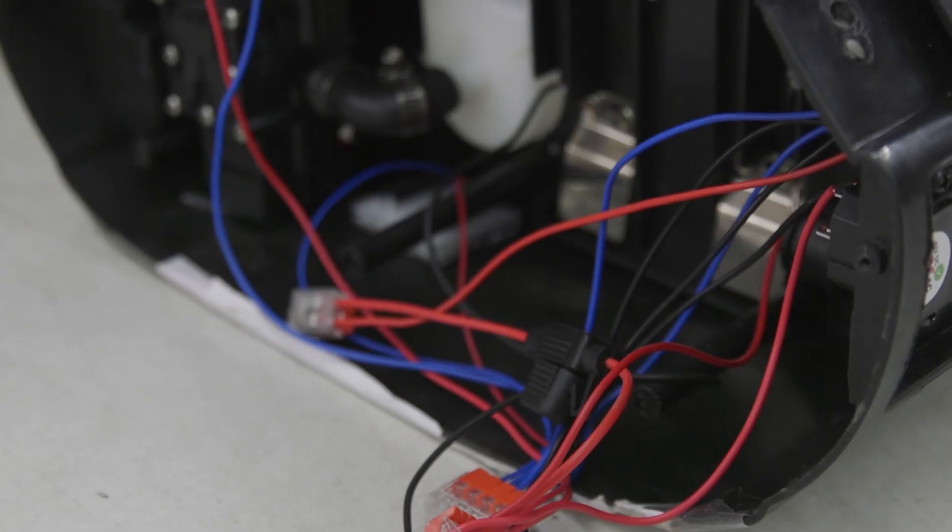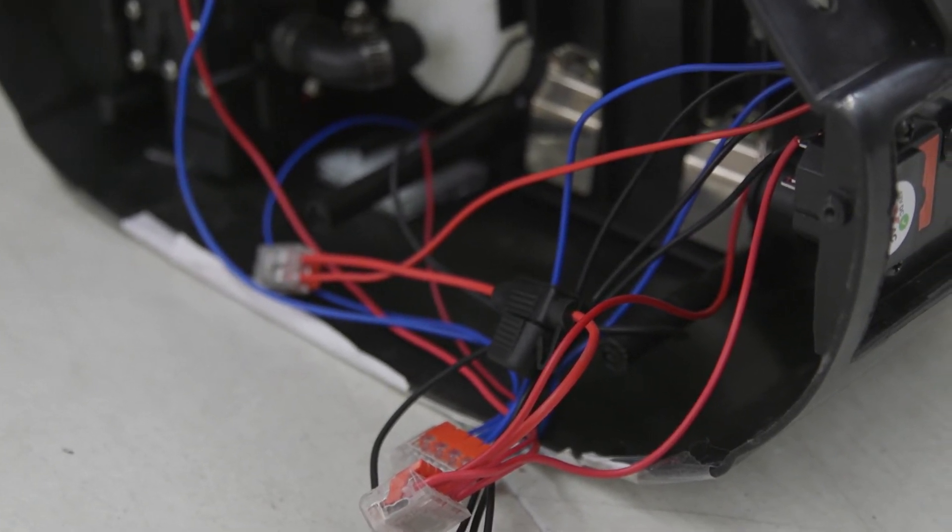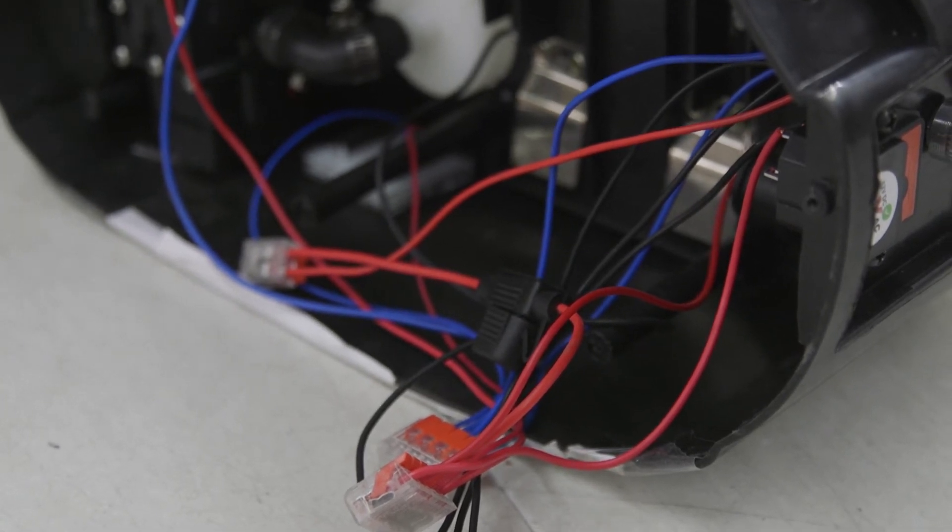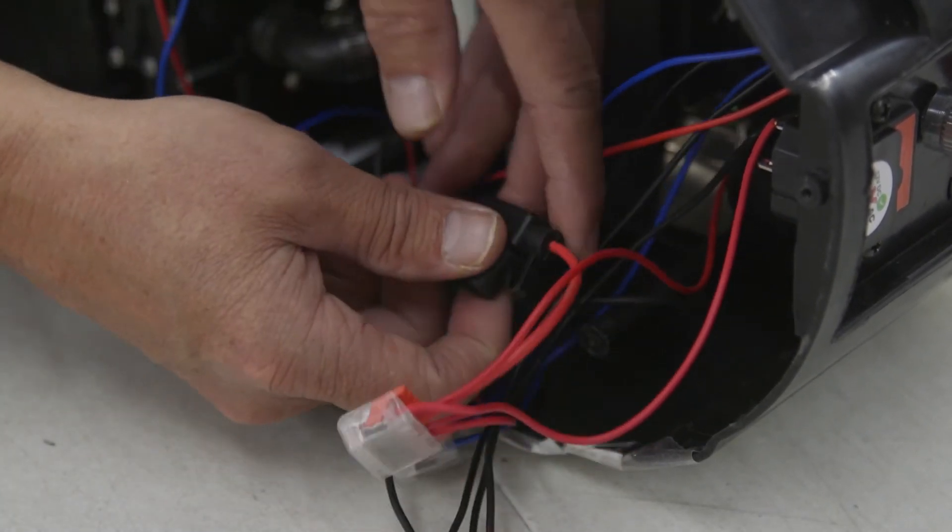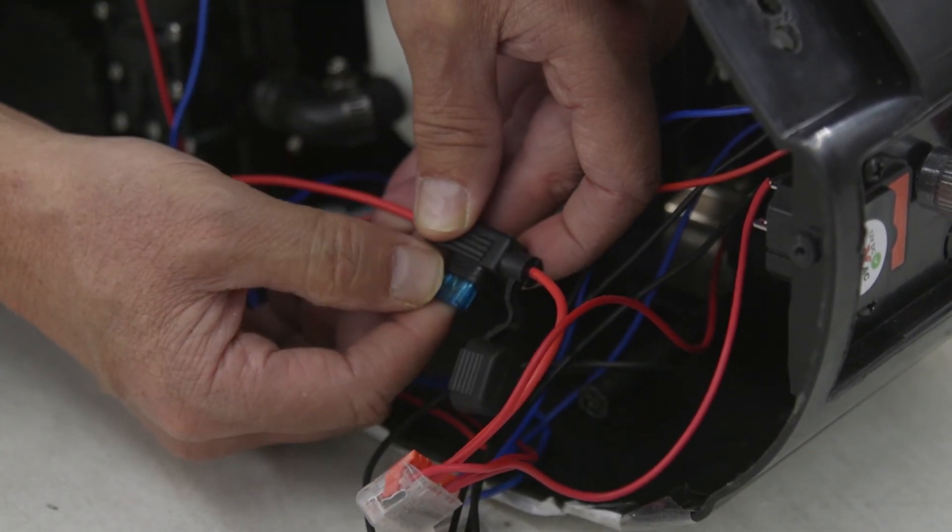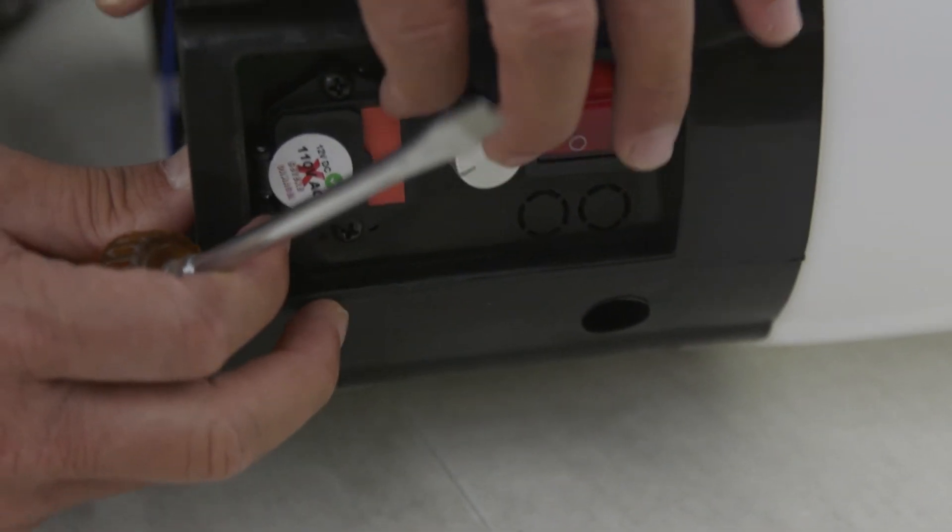If you turn the power switches on and you don't get any voltmeter lights, the first three causes of that are basically the battery connection. If that doesn't solve your problem, double check this fuse which you may have already done. Make sure that it is intact and also double check this red fuse drawer.